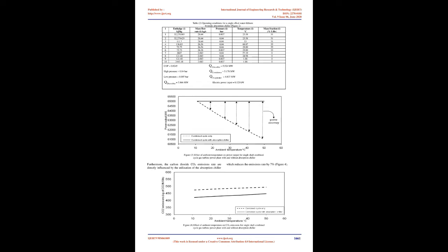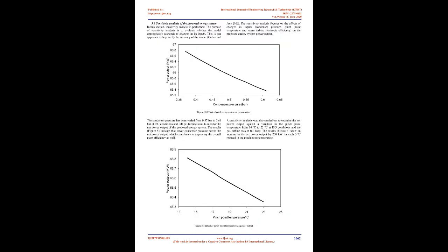3.2 The power plant behavior at off-design conditions. Combined cycle gas turbine power plants often run under off-design situations due to change of the load or ambient conditions or both. Particular attention therefore should be given to analyzing the behavior of the proposed power plant used in this study. This topic is set to investigate the proposed power plant performance under the fluctuating weather conditions, i.e. ambient temperature only. The maximum and minimum values will be considered from the weather data in Libya, to ensure the power plant stability at all extreme weather conditions that may take place.